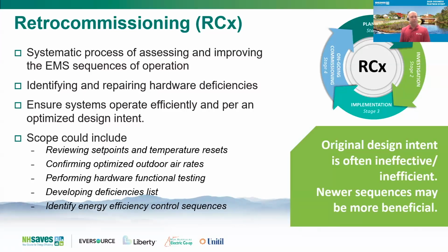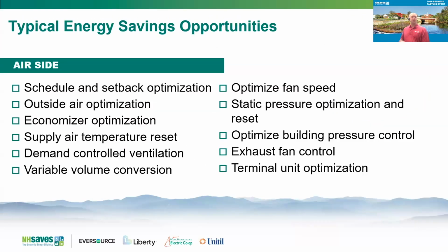Scope should include reviewing set points and temperature resets, confirming outside air rates, looking at hardware functional testing, again, developing a deficiencies list and looking at sequences. So I'm going to flash a few sequence opportunities on the screen. You can get these from the presentation later on, so we're not going to go through these. But on the air side, there's a whole litany of typical sequences from outside air optimization to demand control ventilation, et cetera.